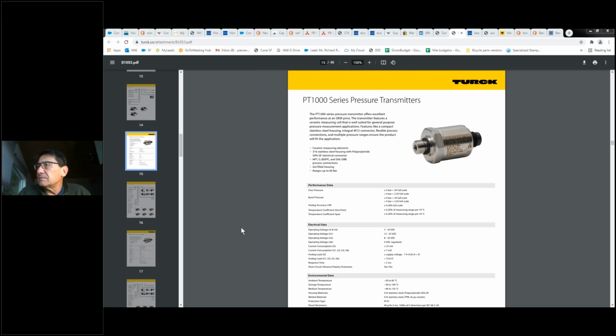Now, back to the sensor. The main issue that I have with the sensors is the fact that the field wiring is, in my opinion, a high-risk issue in terms of future problems. And that makes sense because the human intervention factor is always going to introduce some sort of risk in terms of the performance of a system. And we want to minimize that. We also want to make the job easy.